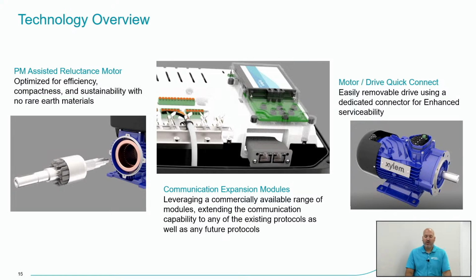So we'll get into the rotor design on the next slide, but here the middle one is just showing you that expansion module. You can see it on the bottom right of the image there, that little gray module. That would be where you would buy that expansion module or communication if you needed something other than Modbus RTU or BACnet MSTP. So you would take the cover off the VFD, a couple screws for that module, but you would put it right in that port.